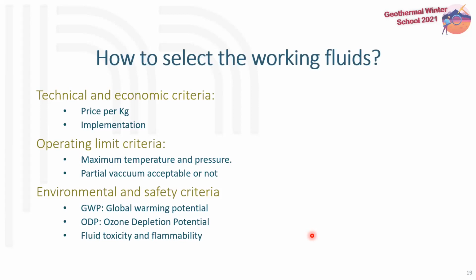You also have the operating limit criteria - the maximum temperature and pressure we can have on your fluids. With some fluids at high temperature, you will burn your fluid and it will lose all its thermodynamic performance. The other limitation is the vacuum need.